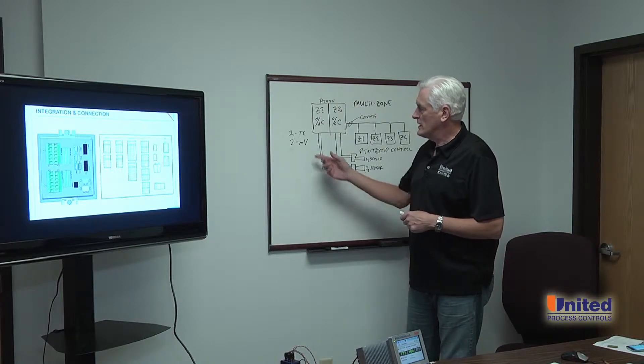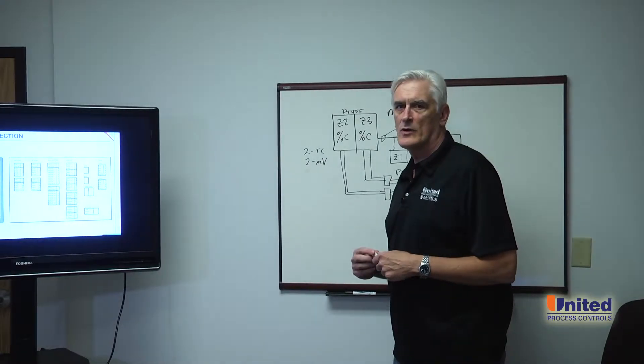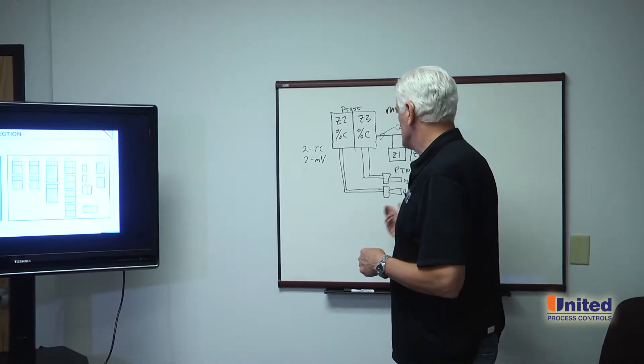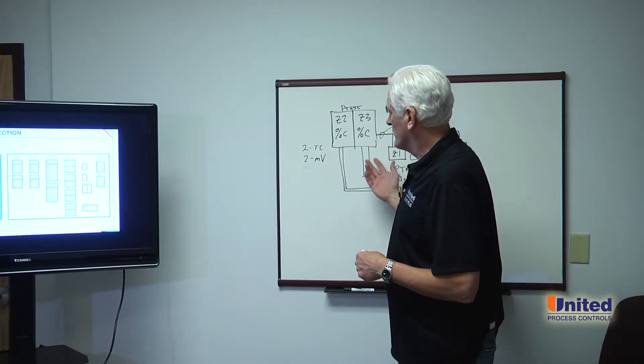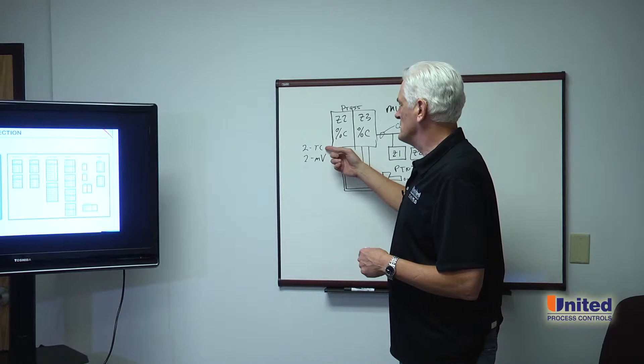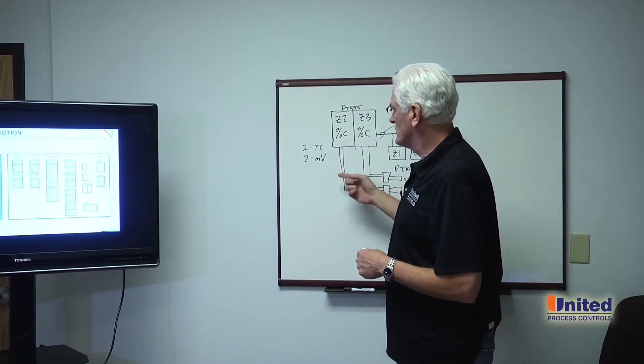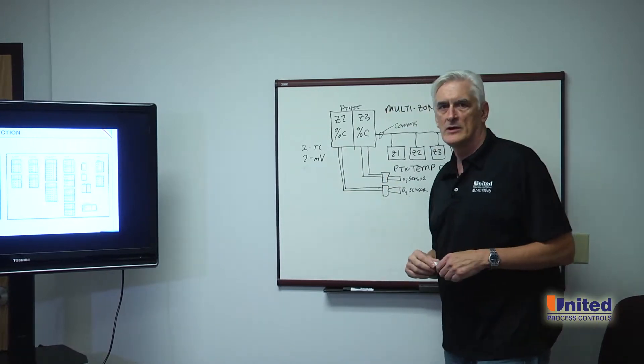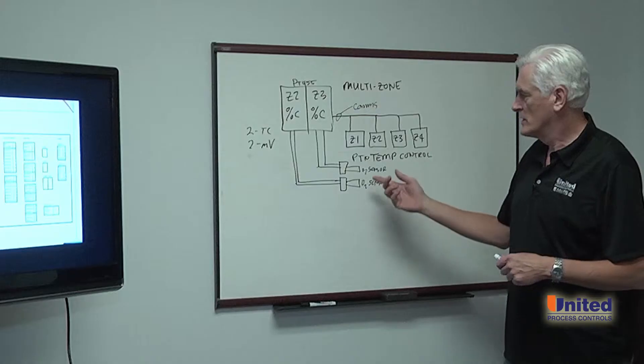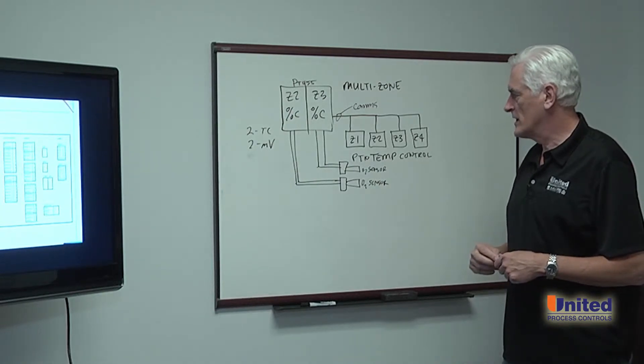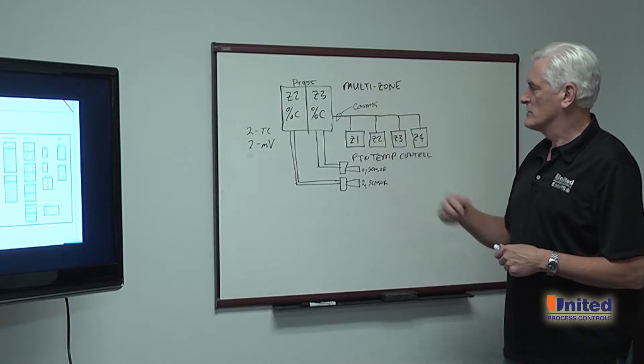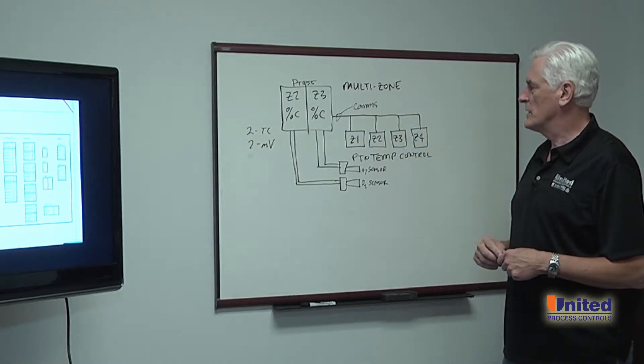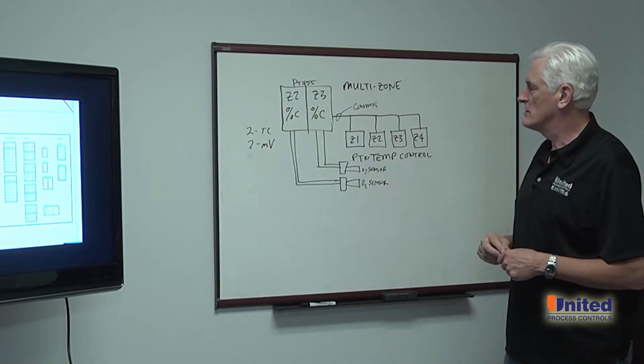The four inputs can be configured for the high impedance requirements of the oxygen sensors we're connecting to the instrument. The four inputs are going to be used for two TC inputs from the sensors and two millivolt inputs from the millivolt output of the sensors.